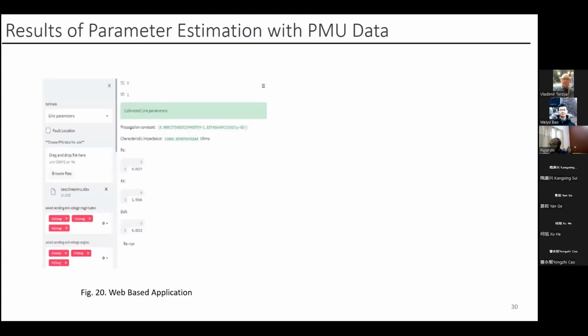And we carry out this exercise also with PMU data. In this case, instead of taking the power flow, we take the line current flow measurements from the PMU as our Z vector, the measurement vector, and we get both voltage and angle from the PMU. However, they are associated with noise, so we use the effective variance formulation.